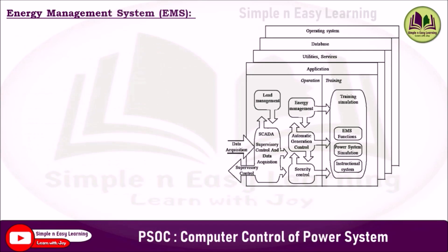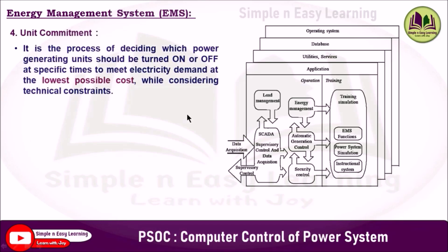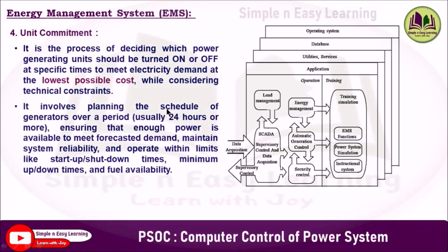The fourth function is unit commitment. It is the process of deciding which power generating units should be turned on or off at specific times to meet electricity demand at the lowest possible cost. Methods such as brute force enumeration and the priority list method can be applied considering technical constraints. It involves planning the schedule of generators over a period — usually 24 hours or more — ensuring enough power is available to meet forecasted demand, maintain system reliability, and operate within limits like startup and shutdown times, minimum up and down times, and fuel availability.